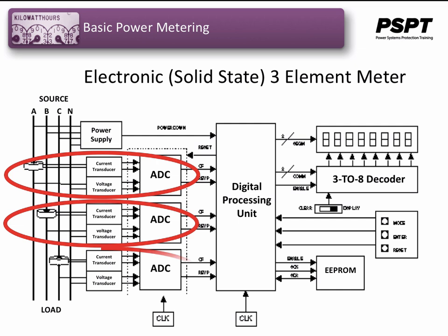As I said, we could use a 3-element meter to accomplish the same thing. Each element measures the phase to neutral voltage across the load and the current into the load. The digital processing unit then sums the total consumption.